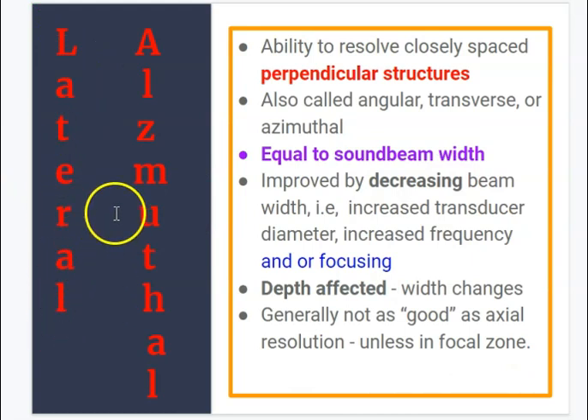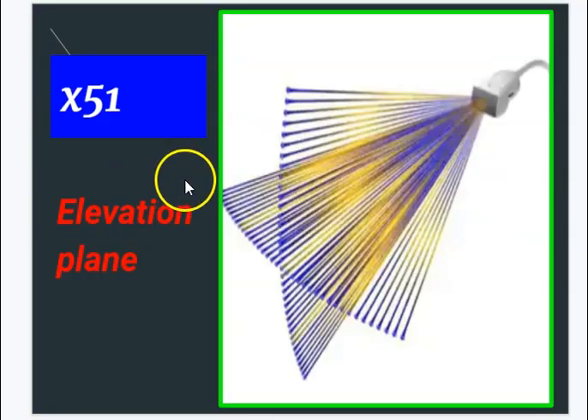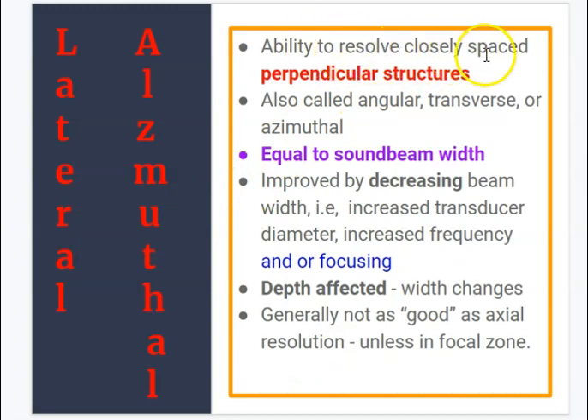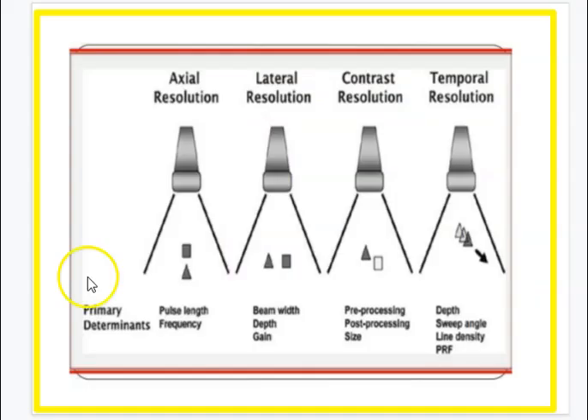With lateral resolution, or azimuthal resolution, remember that's in the azimuthal plane, not the elevation plane. That's the ability to resolve closely spaced perpendicular structures, also called angular, transverse, or azimuthal. So it's perpendicular structures to the beam this way. The beam is sweeping through here, and the ability to resolve these this way.